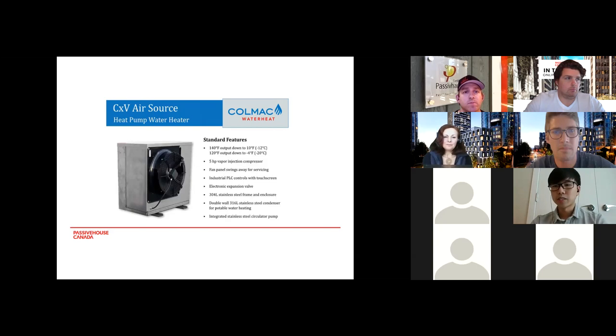But unfortunately, because of the primary energy requirement that Prudence was alluding to earlier, we had to go with a domestic hot water heat pump solution. There are a few manufacturers in our market that supply equipment like this; some prominent ones are Sanden and Colmac. We ended up going with Colmac, as seen on the screen, selecting the CXV low ambient air source model, which was capable of producing domestic hot water at 140 degrees Fahrenheit even when ambient air conditions were as low as 10 degrees Fahrenheit, or negative 12 degrees Celsius.